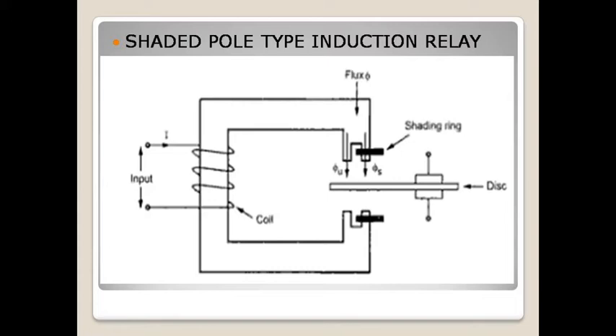That current is sensed by the current coil, and current coil supply is given to the left limb of this induction relay. When current flows through this coil, it produces magnetic flux. The flux is divided into two parts: the unshaded part and the shaded part.